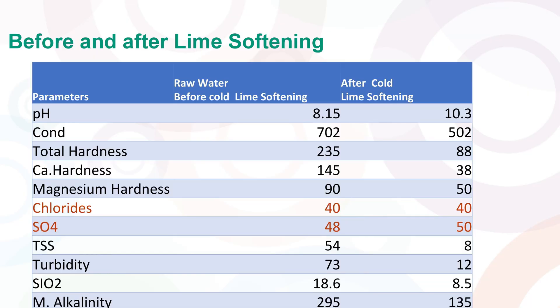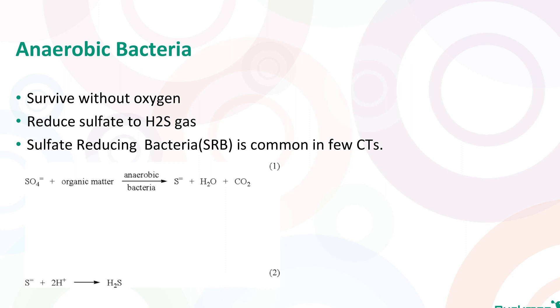Sulfate is a major component of cooling water systems. We add sulfate in cooling towers through sulfuric acid, and our makeup water also contains sulfate ions. In heat exchangers, if sulfate reducing bacteria is present, that bacteria will use the sulfate ion as a food source, converting sulfate ions into H₂S gas. That H₂S gas is very corrosive, and with the passage of time hydrogen sulfide will react with iron metallurgy and convert iron into iron sulfide.